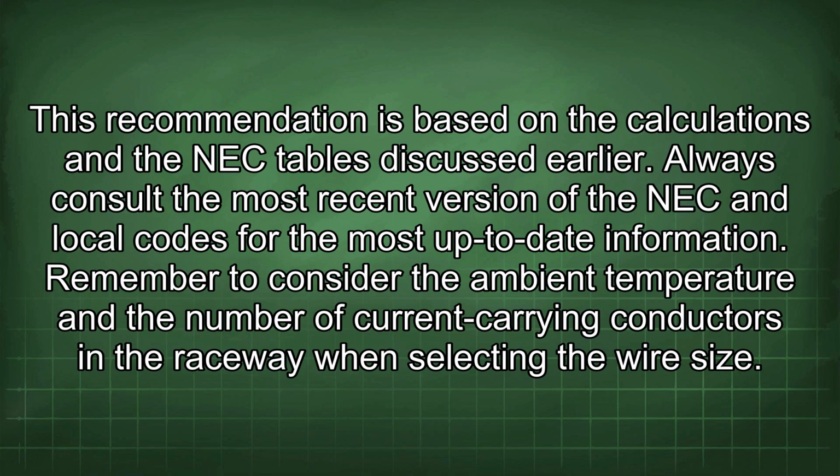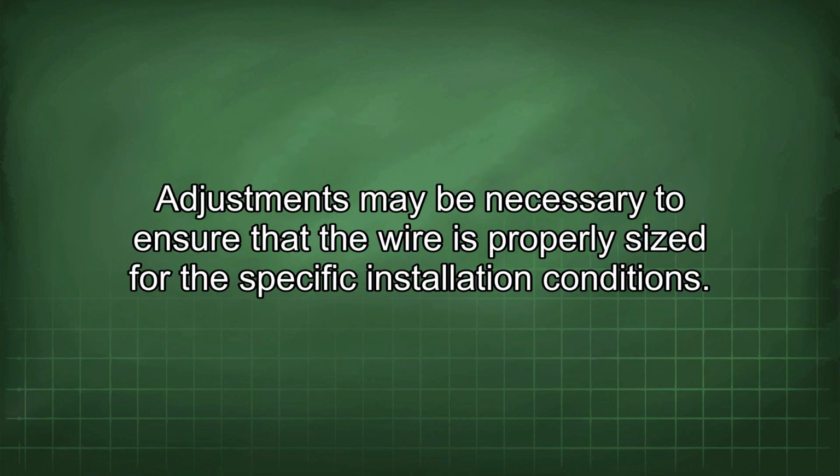Remember to consider the ambient temperature and the number of current carrying conductors in the raceway when selecting the wire size. Adjustments may be necessary to ensure that the wire is properly sized for the specific installation conditions.